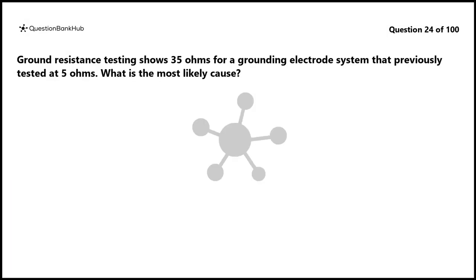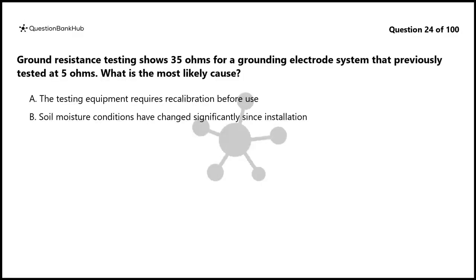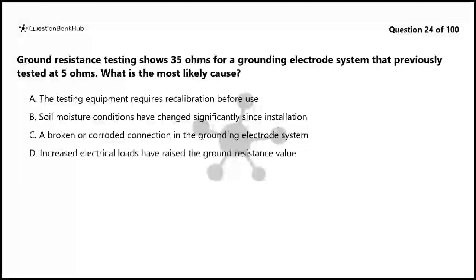Question 24. Ground resistance testing shows 35 ohms for a grounding electrode system that previously tested at 5 ohms. What is the most likely cause? A. The testing equipment requires recalibration before use. B. Soil moisture conditions have changed significantly since installation. C. A broken or corroded connection in the grounding electrode system. D. Increased electrical loads have raised the ground resistance value.